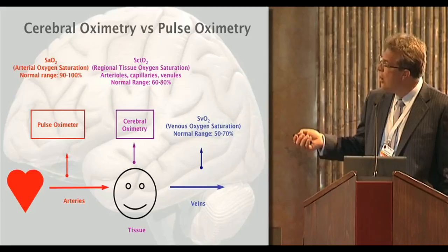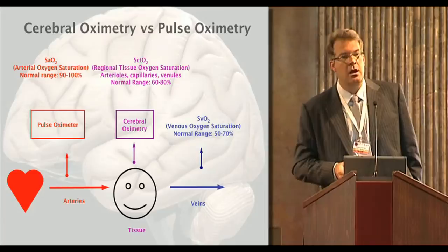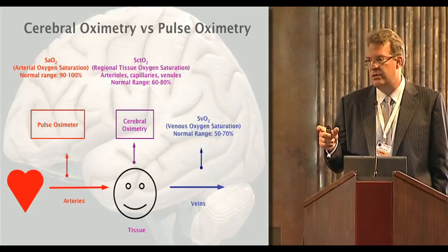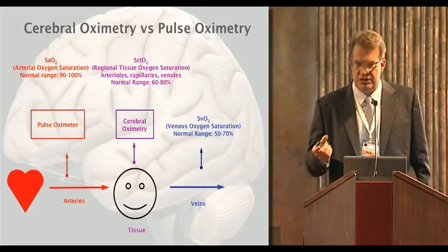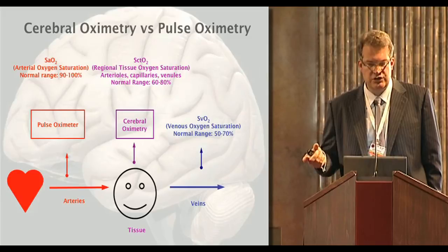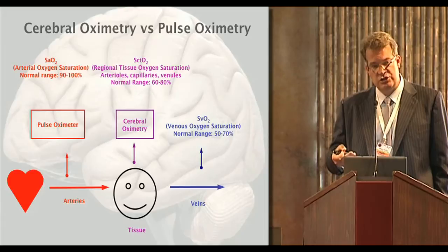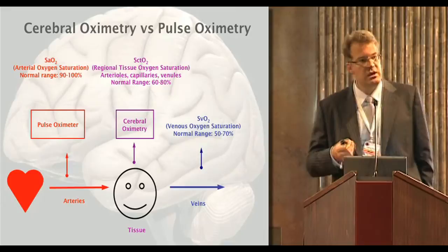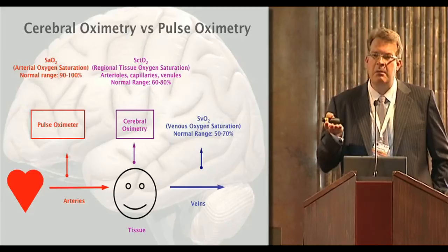Cerebral oximetry is neither arterial nor venous — it's something in between. Through PET studies we were able to look at the blood volume distribution in the brain, and we know that it's about 30% arterial and about 70% venous in most healthy human beings, even during situations of stress. The algorithms developed to calculate cerebral tissue saturations employ this ratio — 30% arterial, 70% venous — so what it really represents is a capillary, or almost a metabolic, value.